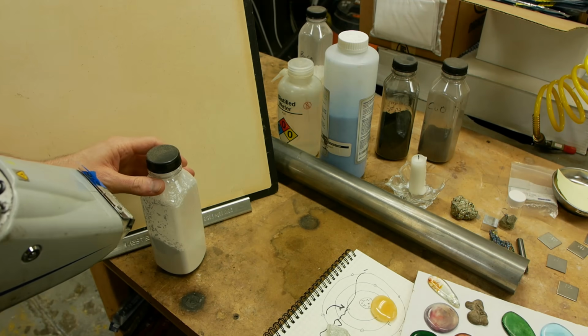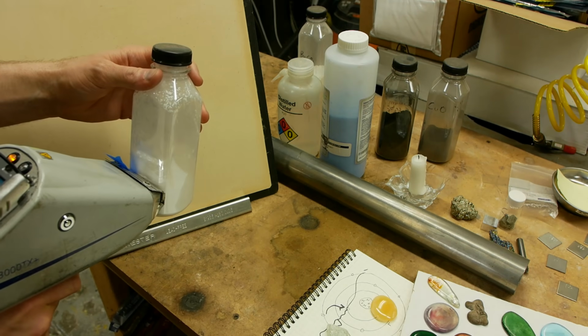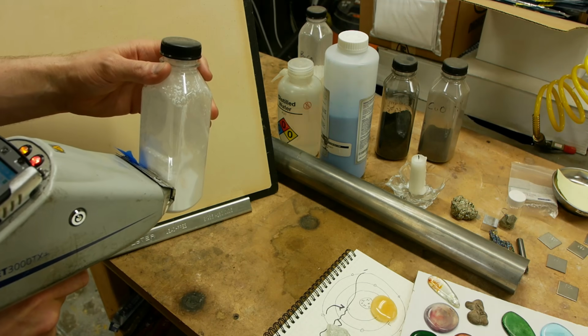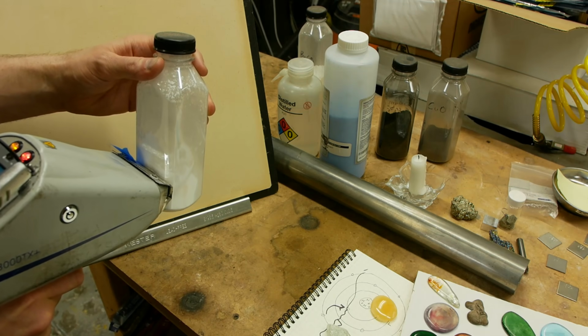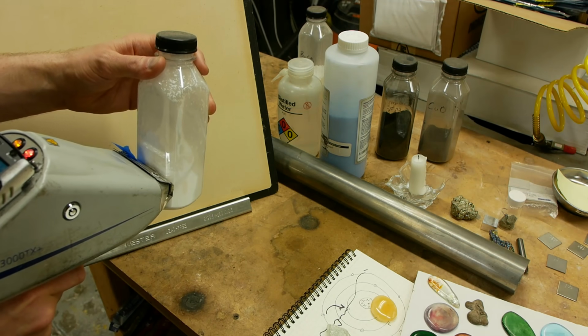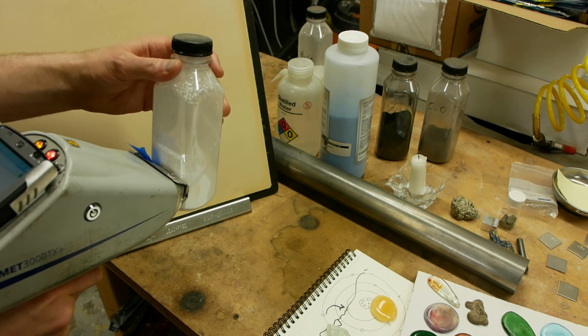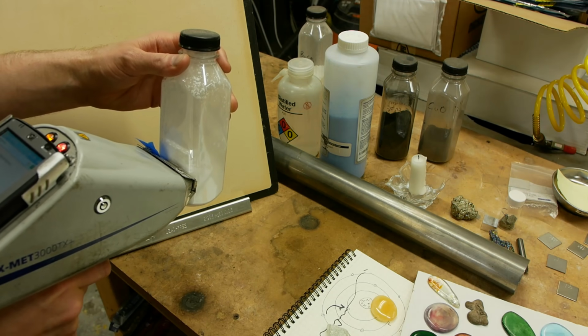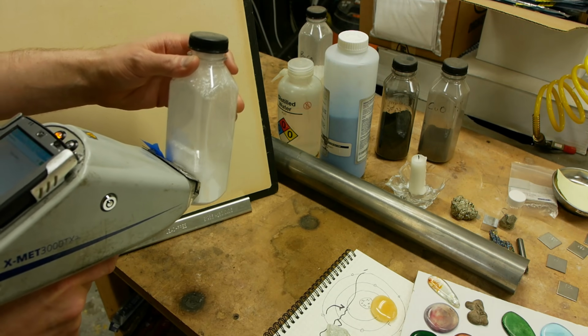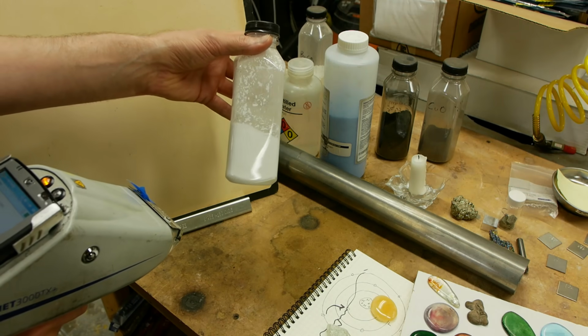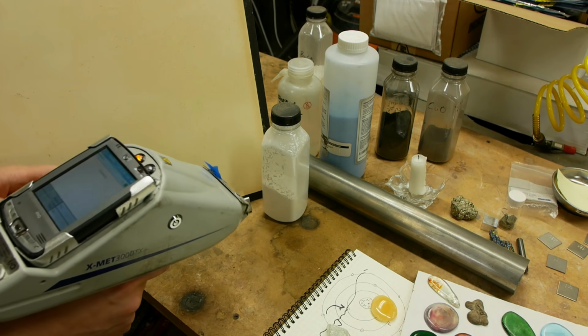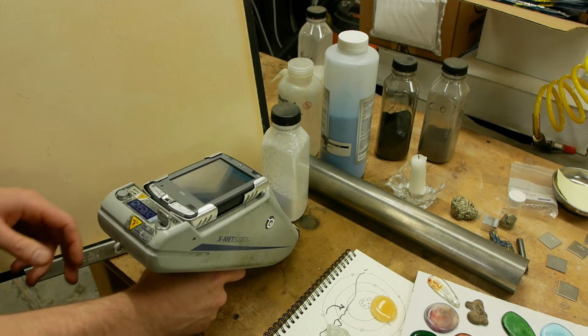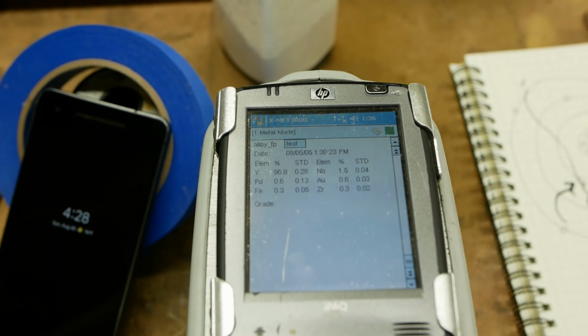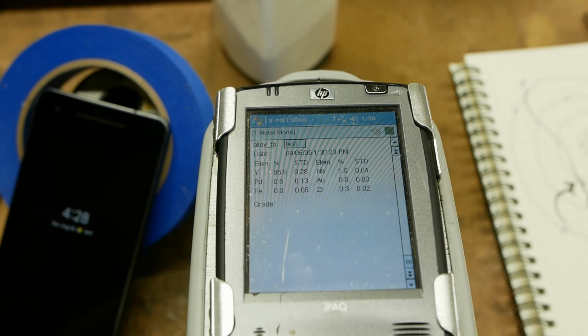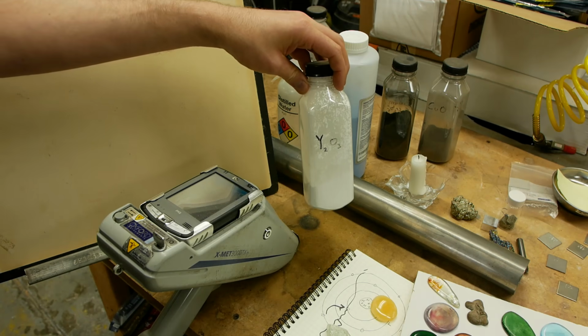I mentioned that the gun also works on compounds, and it even works on powders in a plastic container. The plastic is thin enough and absorbs so little X-ray energy that we get a good signal even through this plastic container. And it's a white powder. We don't know what it is, so we'll wait for the machine to give us some information here. Let's take a look. And as we can see, yttrium, 96.8%. And as it turns out, yeah, it's yttrium oxide in here.